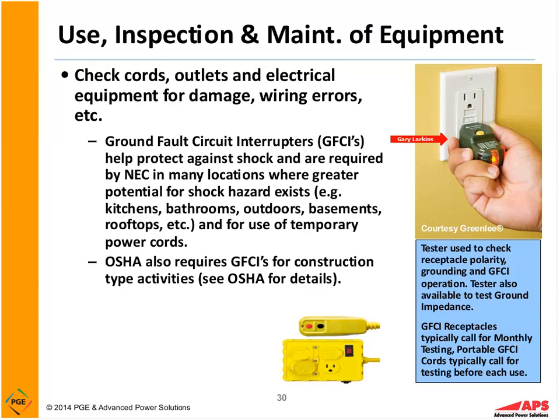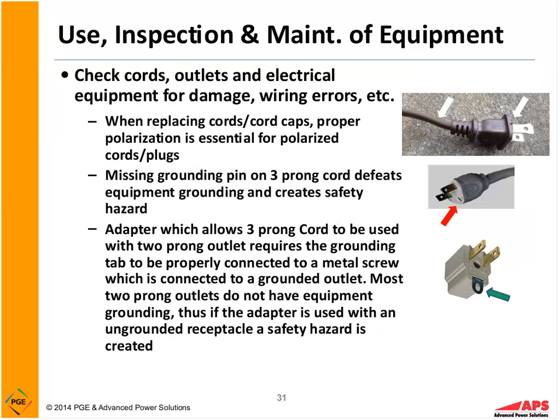You could miswire them and they would not trip during an event when tested. So it's very important we test our receptacles to make sure they're wired properly. If they're not, then we need to get someone that's qualified out to correct those issues. So GFCI is very important for personnel protection.